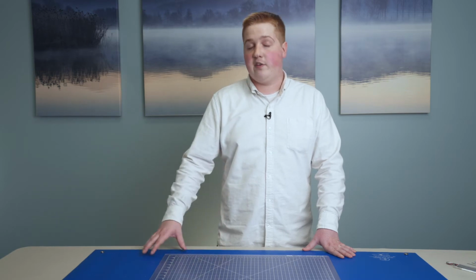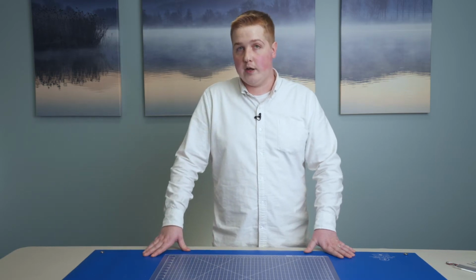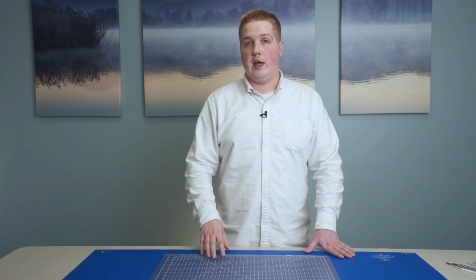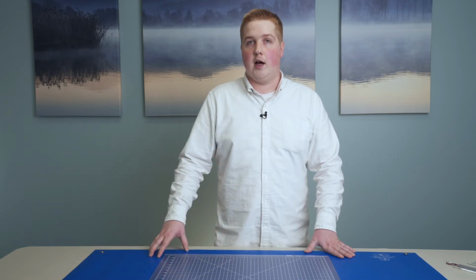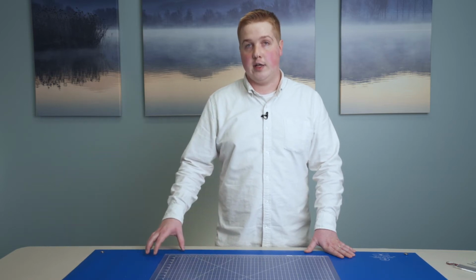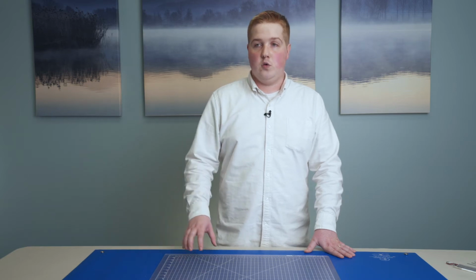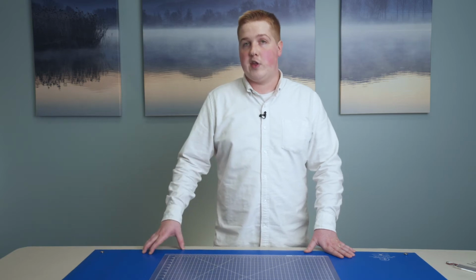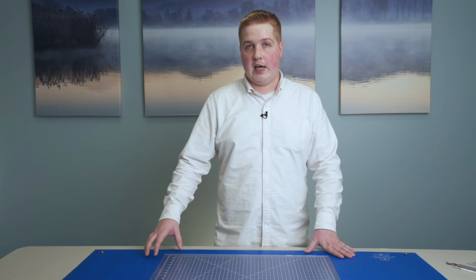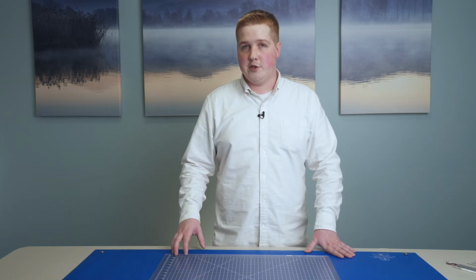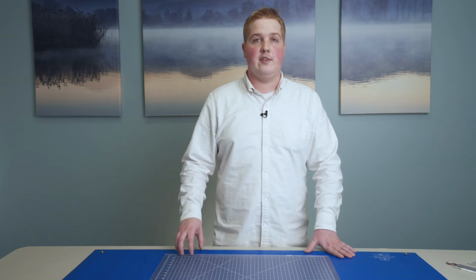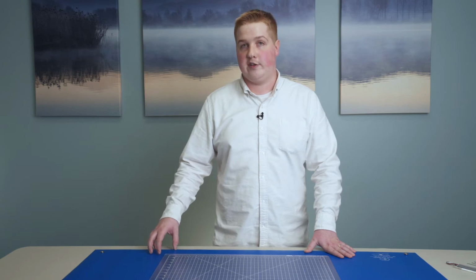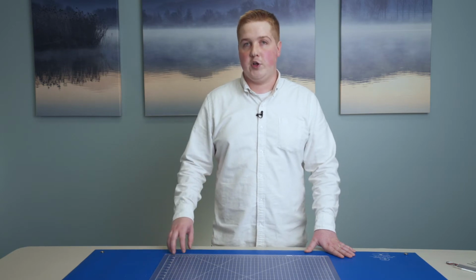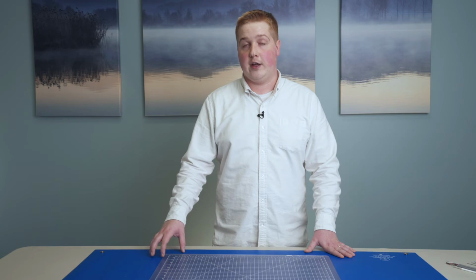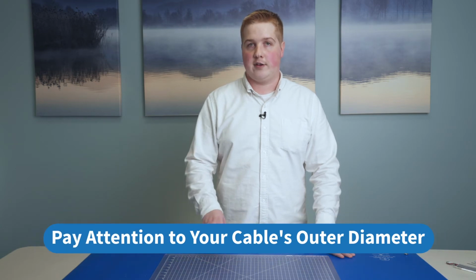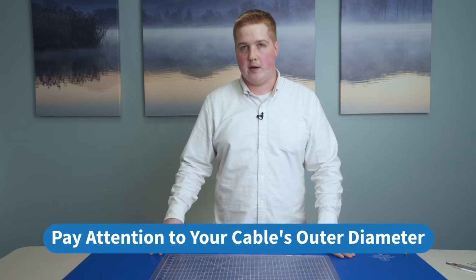Sometimes when you specify something like UL 1015 wire, which comes with a larger voltage rating, but it also comes with a larger insulation diameter. Now, you might be specifying a wire that is on the larger side of the gauge range for the terminal. And unfortunately, that additional thickness in the insulation diameter of the UL 1015 wire can actually put that wire out of spec for that terminal, regardless of the fact that the gauge actually should be compatible.